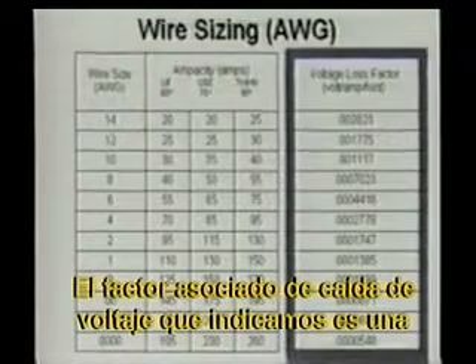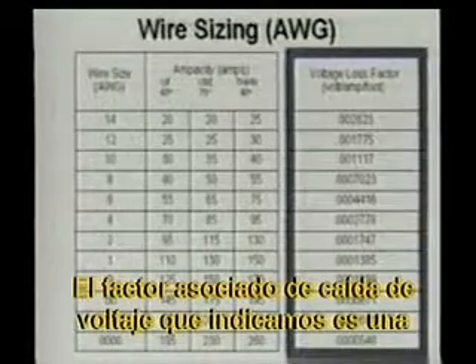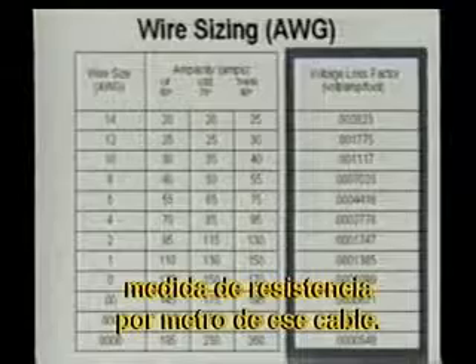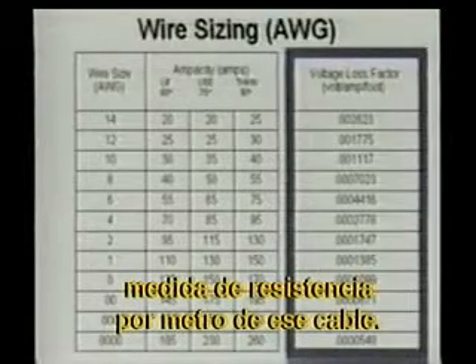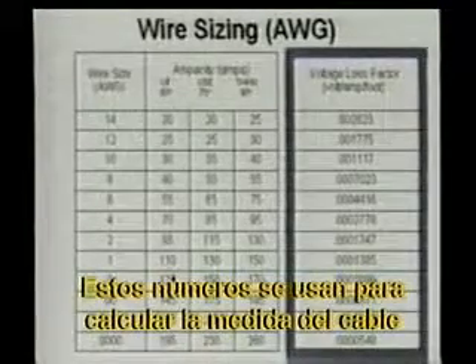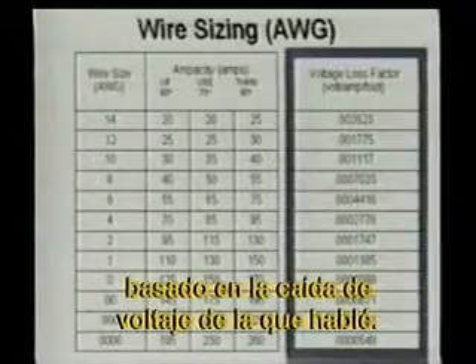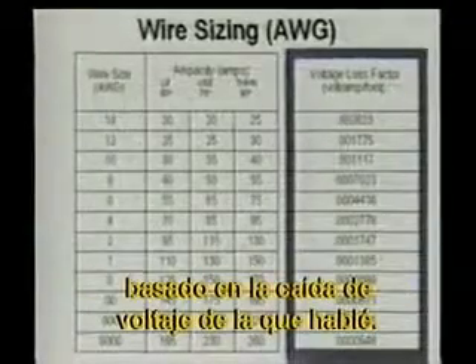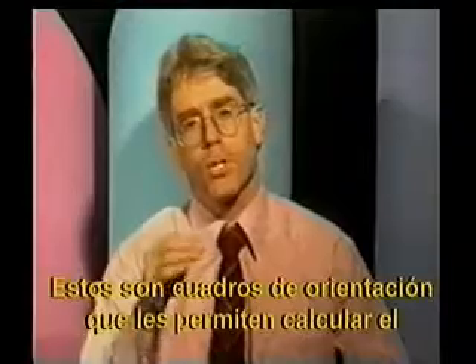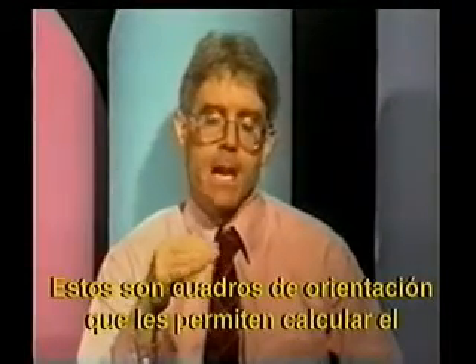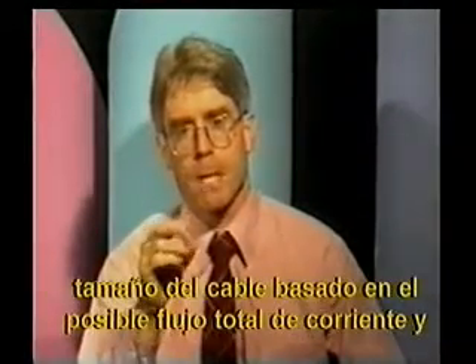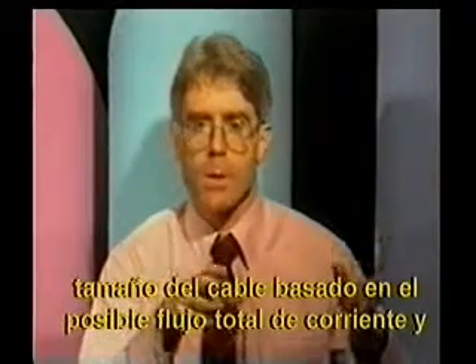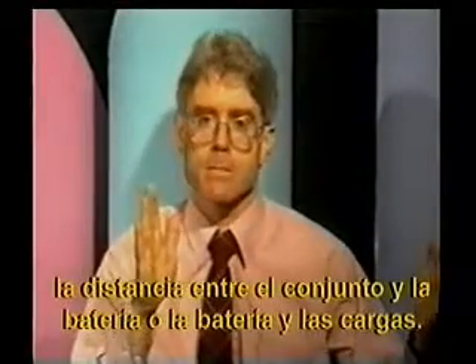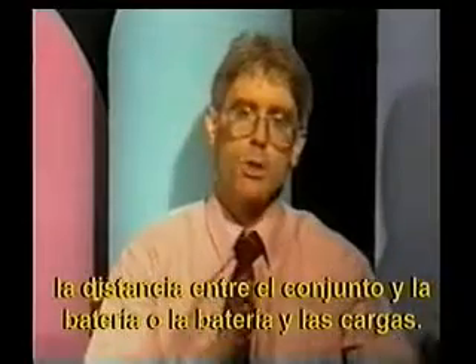The associated voltage drop factor that we've indicated is a measurement of resistance of that wire per foot or per meter. These numbers are used for the wire sizing based on voltage drop that I've talked about. We've created for you some guideline charts that allow you to size your wire based on total current that might be flowing and distance between your array and your battery, or your battery and your load.